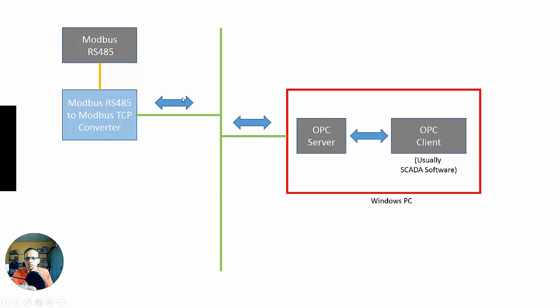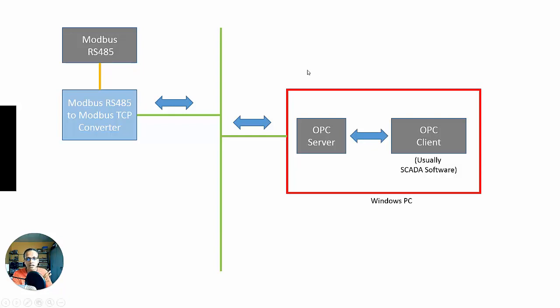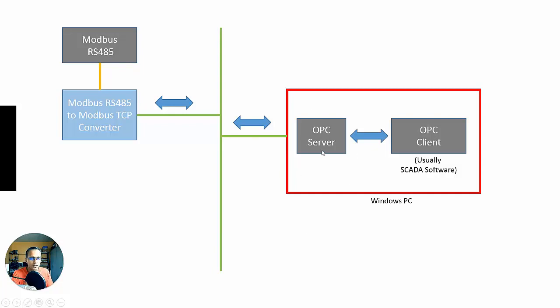In this case, it would be converting from Modbus TCP to the OPC standard, and the OPC client would then be able to communicate with the OPC server, not caring exactly where the data was coming from. That's the magic of classic OPC. Good, and this worked very well. And in this scenario, the OPC server and the OPC client, being classic OPC, are stuck on Windows. They can't run anywhere else. Must be Windows.